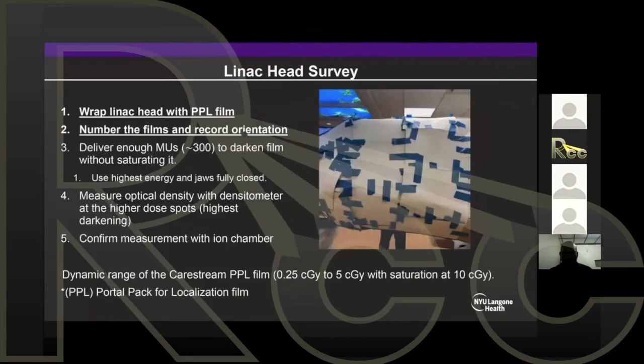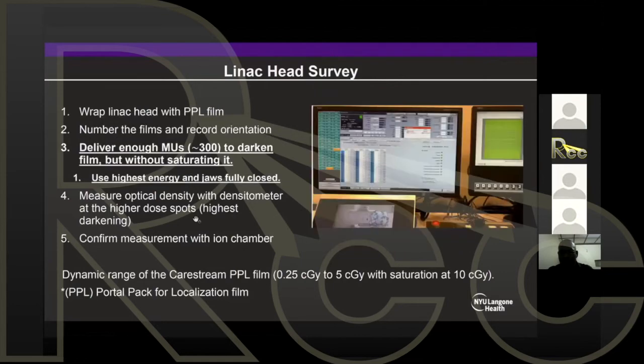The way to do this is to wrap the Linac head with the portal localization film. It's important to number the films, so maybe you can see here 13, here 5. You need to number those films and note the orientation of the films. Then you deliver enough MUs to darken the film, but without saturating it. I think we did around 300 MUs. And here I put which film we used and the limits.